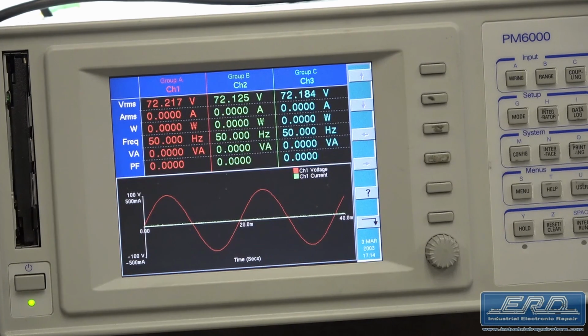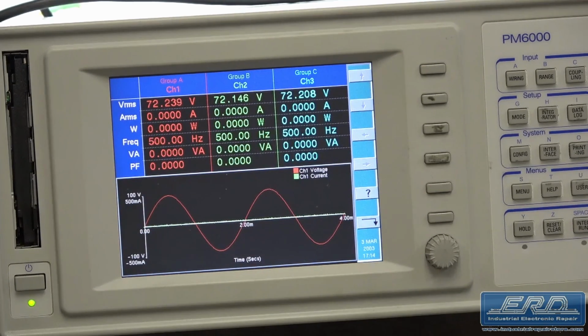These instruments are software-based in terms of their calibration, but we at ERD have been able to adjust the individual channels for calibration data by developing our own software system for interfacing to the instrument. As seen in this video, we are checking out the 3 channels at the 1 range value voltage settings using a power amplifier with different frequencies, since these systems have a very broad spec range.